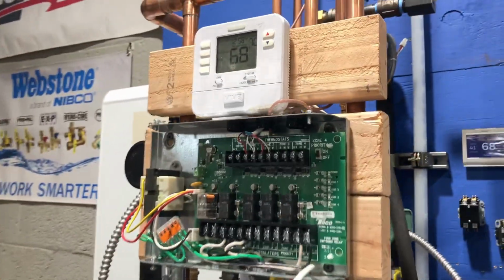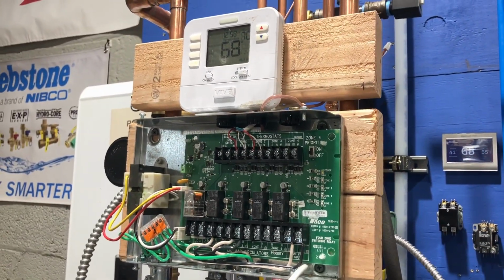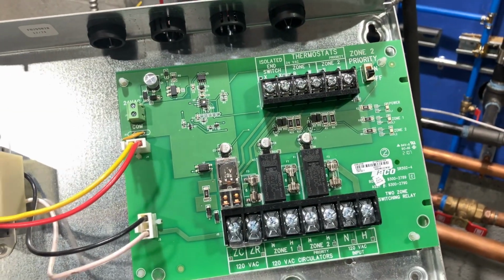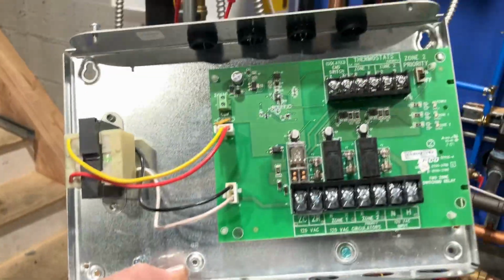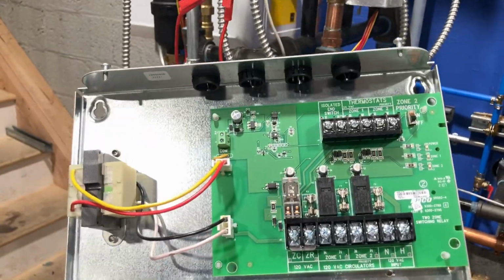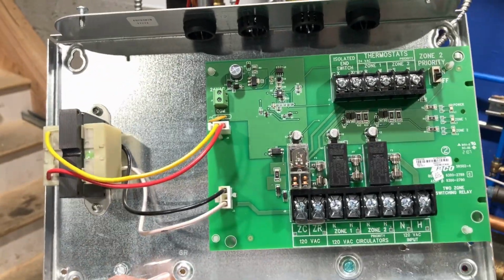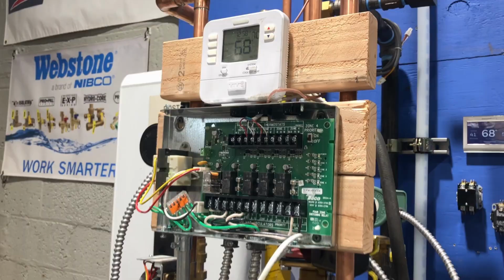So conveniently, this is an SR504 4-zone switching relay. This is an SR502 2-zone switching relay. We only need 2 zones. I only got a 2 zone in my truck. We're going to put in the 2 zone, taking out the 4. And hopefully the problem goes away and we don't have any other callbacks here.